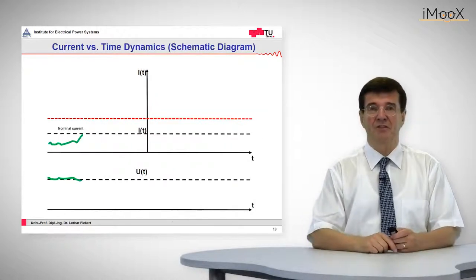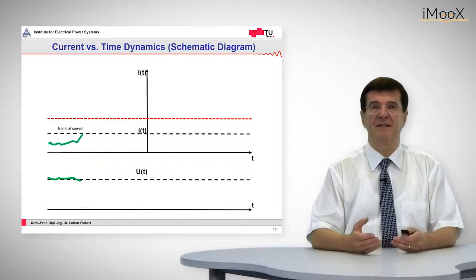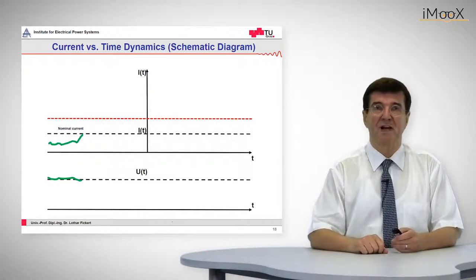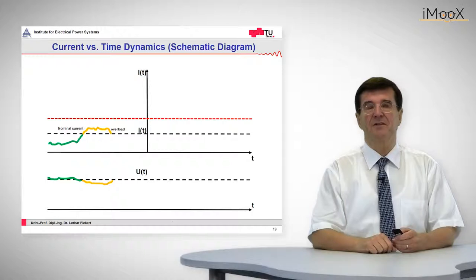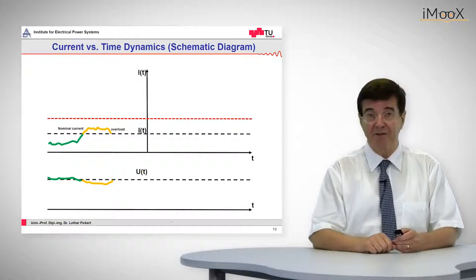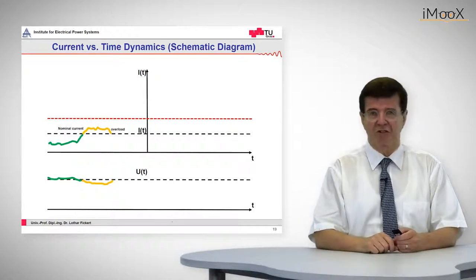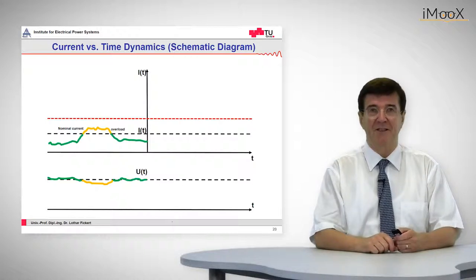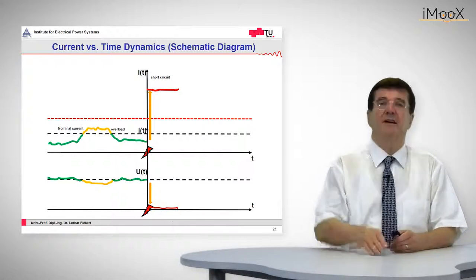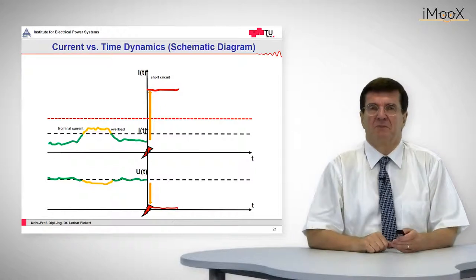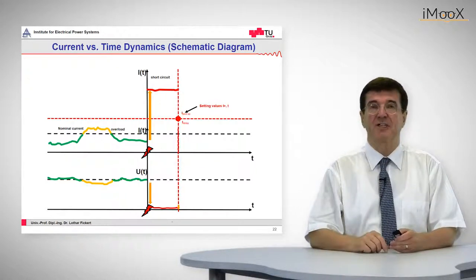Now let's see in terms of voltages and current what happens. First we start with normal operation — everything is in the so-called green range. The voltages are more or less okay and the current is below its nominal value. If the current goes above the nominal value, which is given by the dotted line, then we speak about overload, and suddenly at a certain time it goes back to normal operation. And now this short circuit occurs: the voltage breaks down and the current goes up to values of some typical kilo-amps, for example 5 kilo-amps.